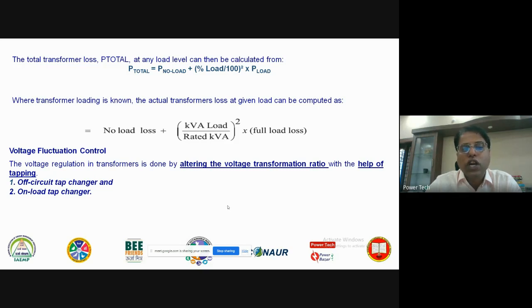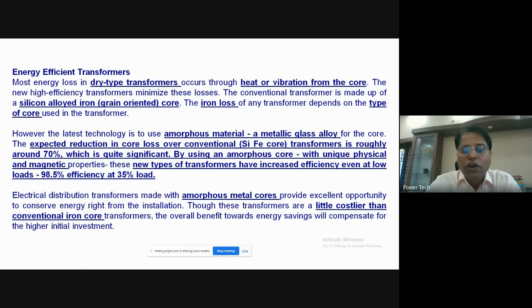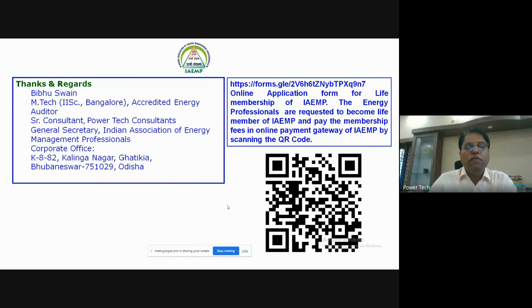And there are two things we need to control: the voltage fluctuation, by using OLTC or off-load tap changers. And we have heard about energy efficient transformers. Sometimes a transformer is over-designed and it operates at 35% to 40% load, but we have studied that transformers are efficient at 70% load. So a few technologies like amorphous material and metallic glass alloys have come forward, which can give 98.5% efficiency even at 35% load. So in our audit reports, we recommend this type of transformer where the load is a little less, and these are all dry type transformers having amorphous metal cores. This is one technology which we have already studied, and we will learn about different technologies.